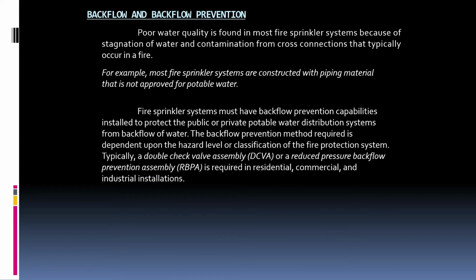The next one is backflow and backflow prevention. Poor water quality is found in most fire sprinkler systems because of stagnation of water and contamination from cross connections that typically occur in a fire. For example, most fire sprinkler systems are constructed with piping material that is not approved for potable water. Fire sprinkler systems must have backflow prevention capabilities installed to protect the public or private potable water distribution systems from backflow water. The backflow prevention method required is dependent upon the hazard level or classification of the fire protection system. Typically, a double check valve assembly, or DCVA, or a reduced pressure backflow prevention assembly, or RPBA, is required in residential, commercial, and industrial installations.